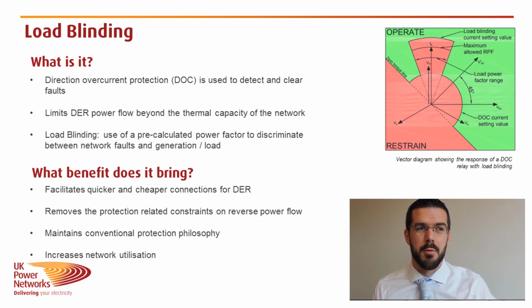Quite often on our 132,000 volt and 33,000 volt networks, we use a technology called Directional Overcurrent Protection, or DOC for short, to detect upstream faults on our network. This can limit the amount of power that's allowed to flow upstream through a transformer, and this might be lower than the thermal limit, or the amount of power that the transformers, cables and overhead lines can cope with.